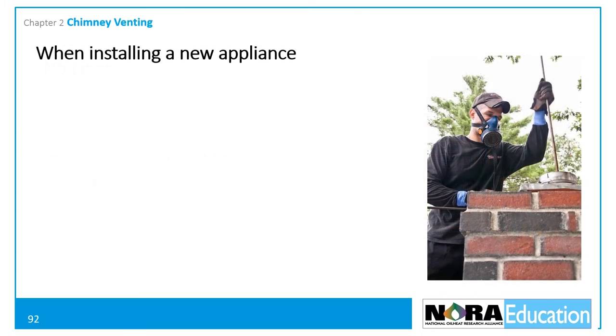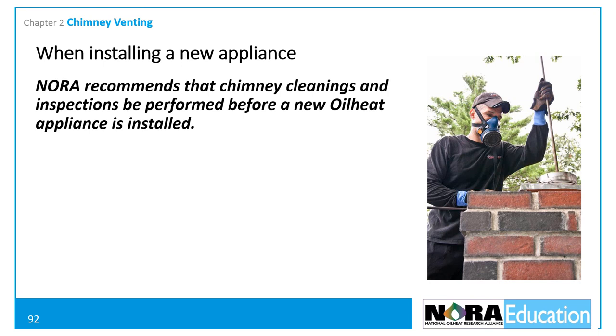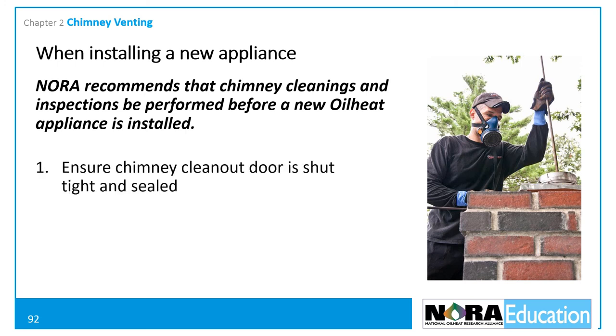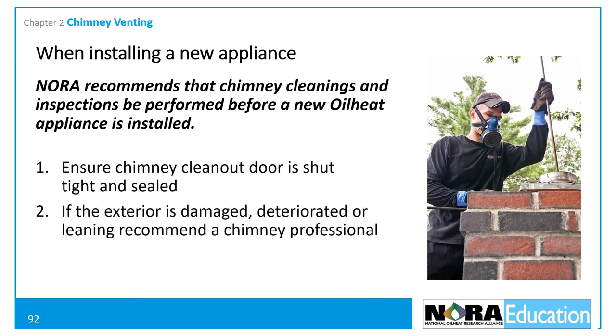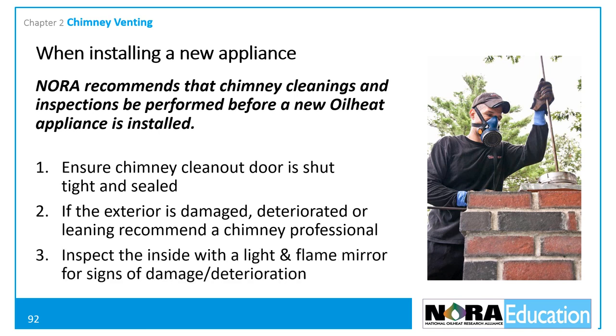This next section covers steps to take when installing a new oil heat system into a chimney. NORA recommends that chimney cleanings and inspections be performed before a new high-efficiency oil heat appliance is installed to replace an older unit. The inspection should include: making sure any clean-out door is shut tight and sealed; observing the exterior of the chimney — if it is damaged, deteriorating, or leaning, further inspection by a chimney professional should be recommended; and removing the flue pipe from the chimney breech and inspecting the inside with a light and a flame mirror for signs of damage or deterioration.